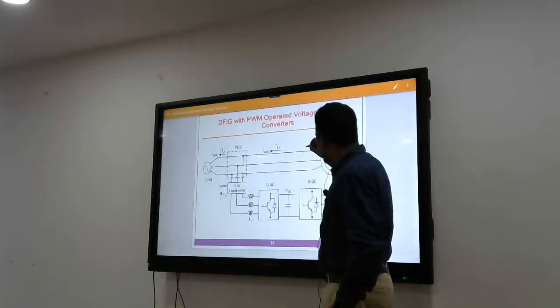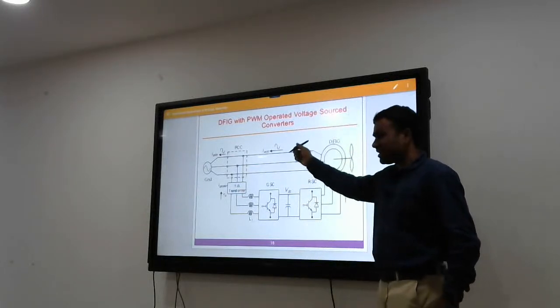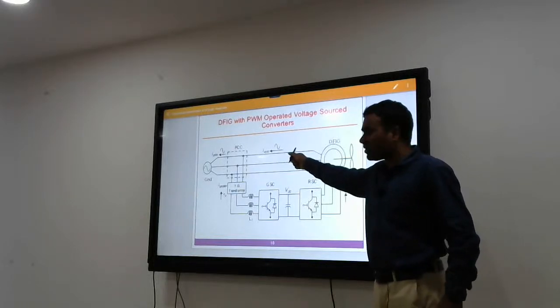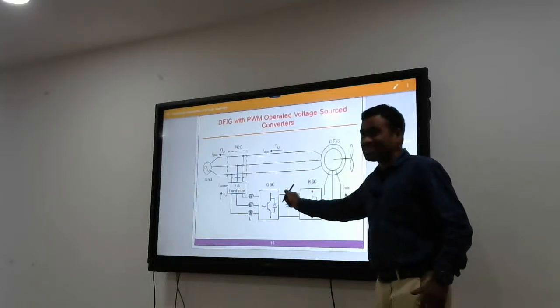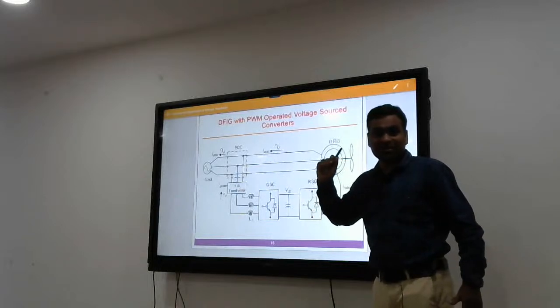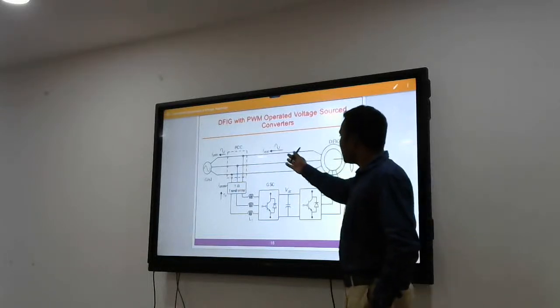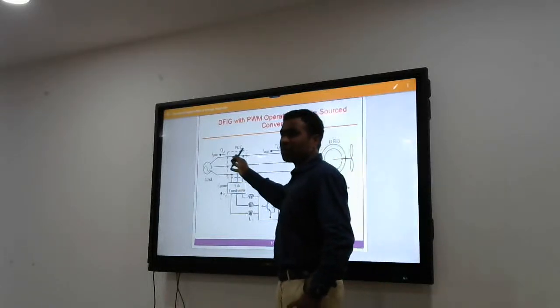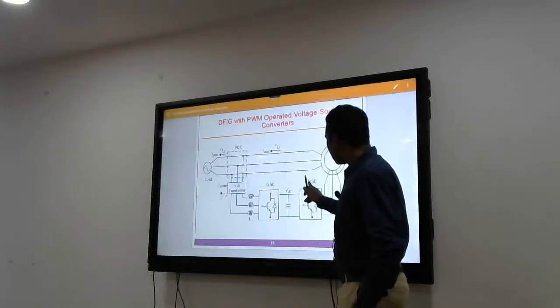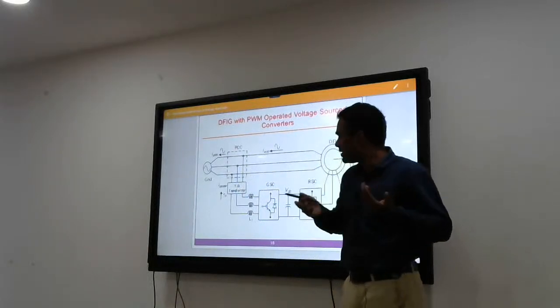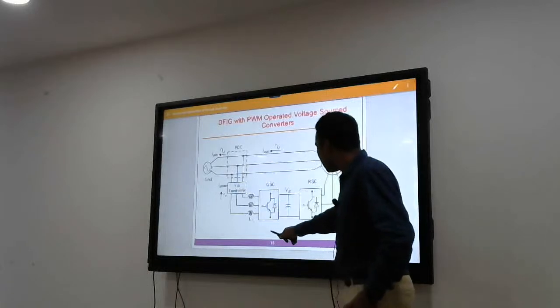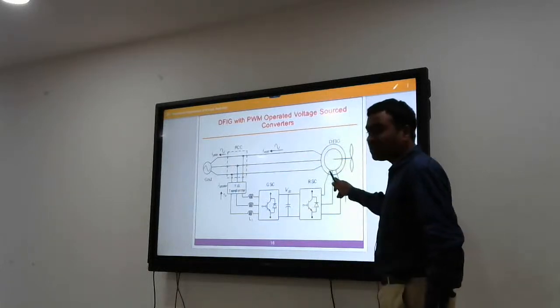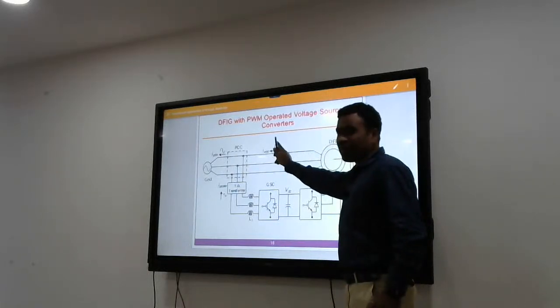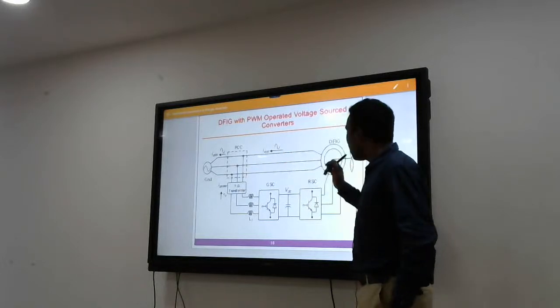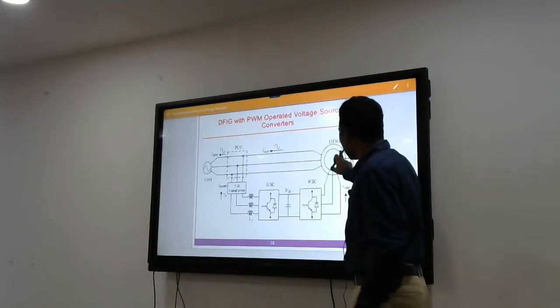I can change my stator power. I have to change my stator power with the help of these converters that are placed in the rotor side, because you don't have any control over here. Here, what can you change? You can change the voltage and current, whatever you want, in the rotor side only. But that should affect your stator power. How? By controlling the rotor currents.